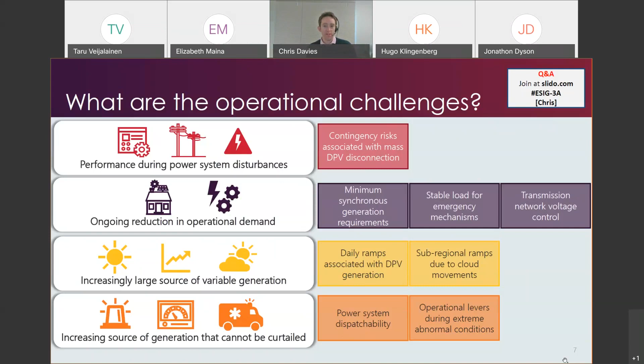The last area then is the fact that distributed PV is a source of generation at the moment that can't be actively managed or curtailed. So this, for us as system operator, reduces the operational levers available for helping us keep supply and demand balanced during normal operation. And it also raises questions about how we maintain sufficient operational levers to rapidly rebalance the system during some extreme abnormal system conditions. So here we're thinking about high solar, low underlying demand days on a spring weekend combined with an interconnector outage, which would leave us really exposed if we were then to experience a contingency event on the system. I think Hugo and Elizabeth will touch a little bit more on some of these challenges. Next slide, please.